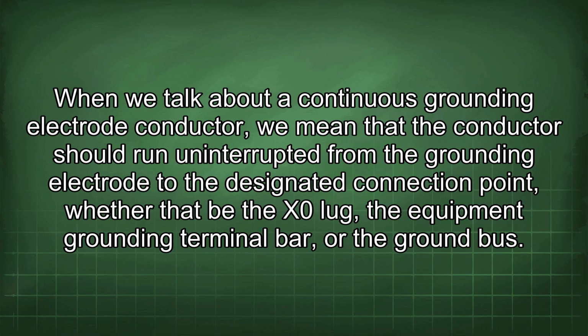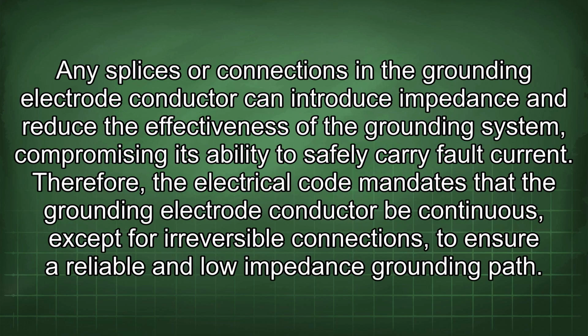When we talk about a continuous grounding electrode conductor, we mean that the conductor should run uninterrupted from the grounding electrode to the designated connection point, whether that be the X0 lug, equipment grounding terminal bar, or the ground bus. Any splices or connections in the grounding electrode conductor can introduce impedance and reduce the effectiveness of the grounding system, compromising its ability to safely carry fault current. Therefore, the electrical code mandates that the grounding electrode conductor be continuous except for irreversible connections to ensure a reliable and low impedance grounding path.